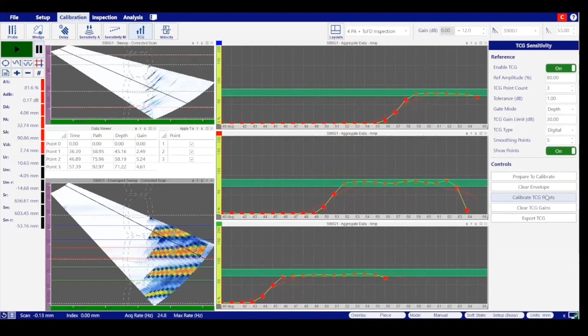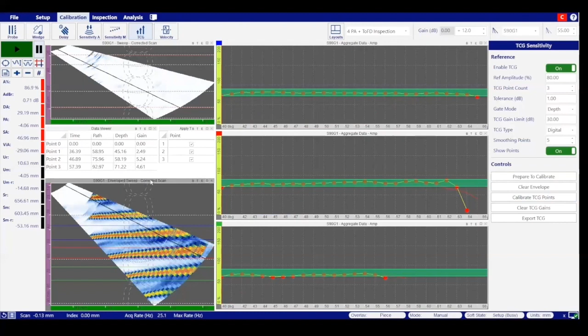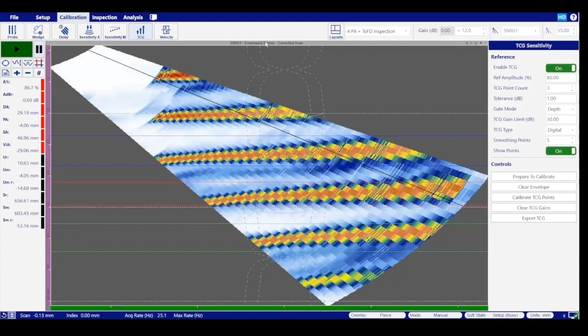Once we hit calibrate, we can re-verify our signal. You can see all 3 are simultaneously adjusted in gain and compensated for that attenuation. Okay. So we can double click on the scan and re-verify. Give me a second. Yeah. So this also helps you complete your TCGs much faster, but we also have the manual TCG, which is the regular way of doing it.